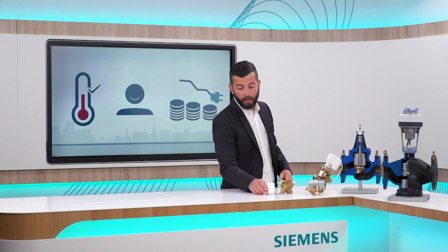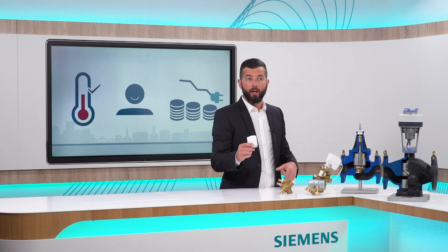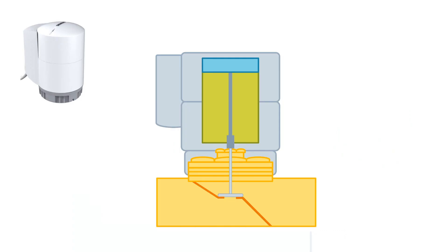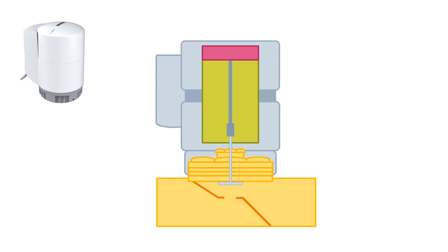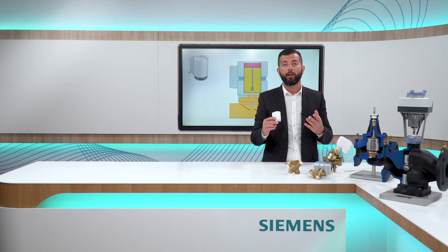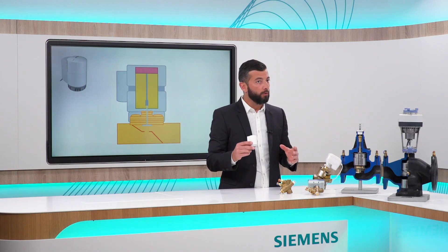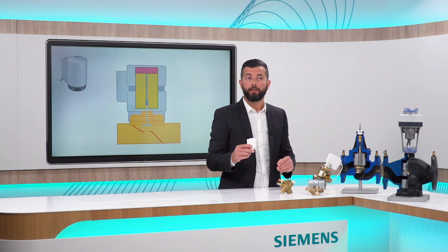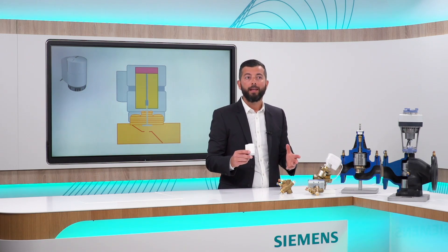Here, a thermal actuator could be a good choice. Thermal actuators are basically temperature-operated devices, where electricity heats up a Wax cartridge which expands and retracts. This kind of actuator is quite slow compared to other technologies, but also very quiet — perfect for noise-sensitive environments and therefore ideal for chill beams.